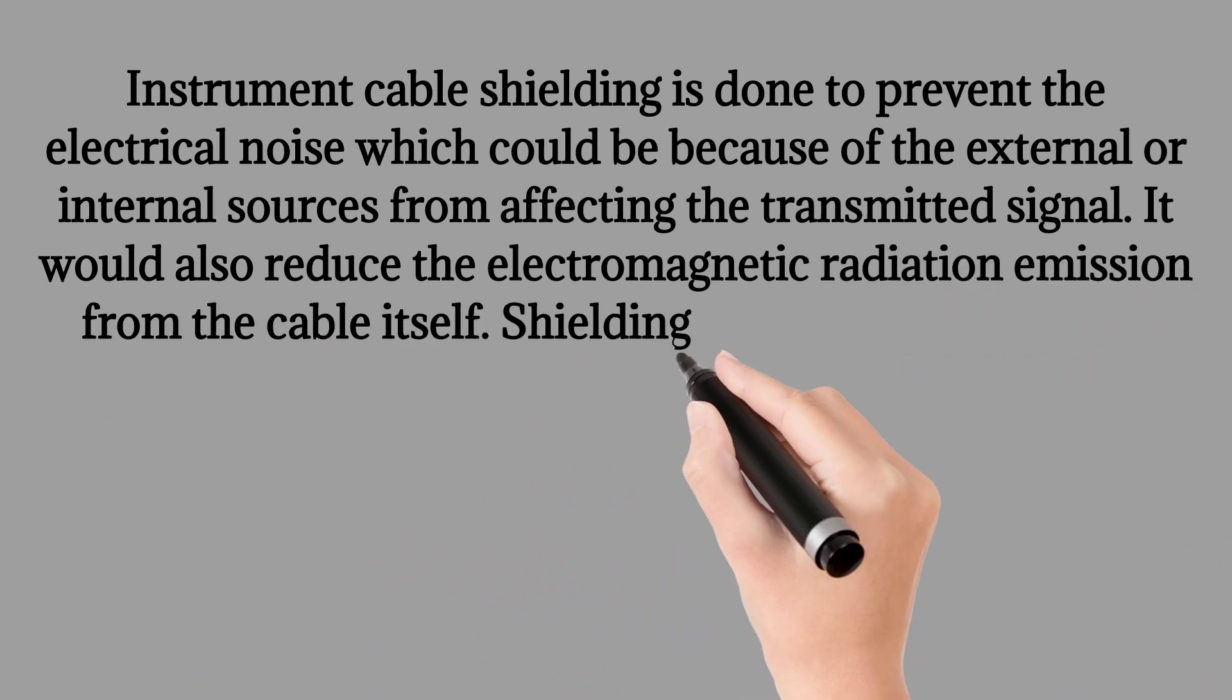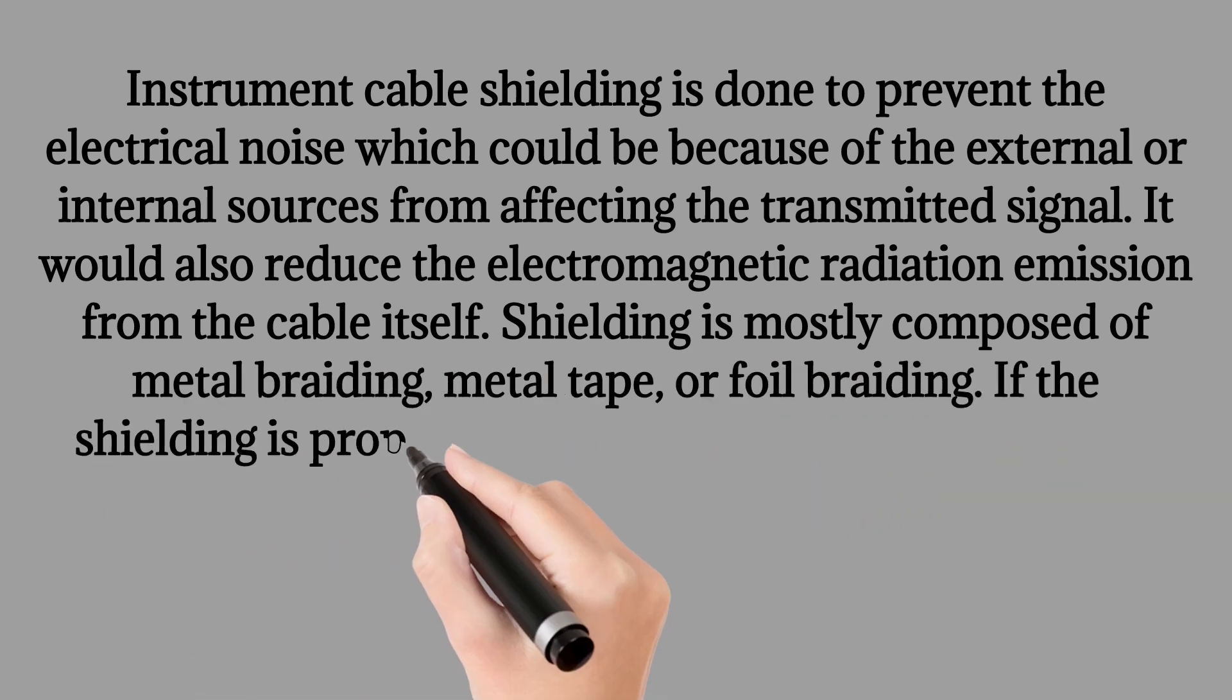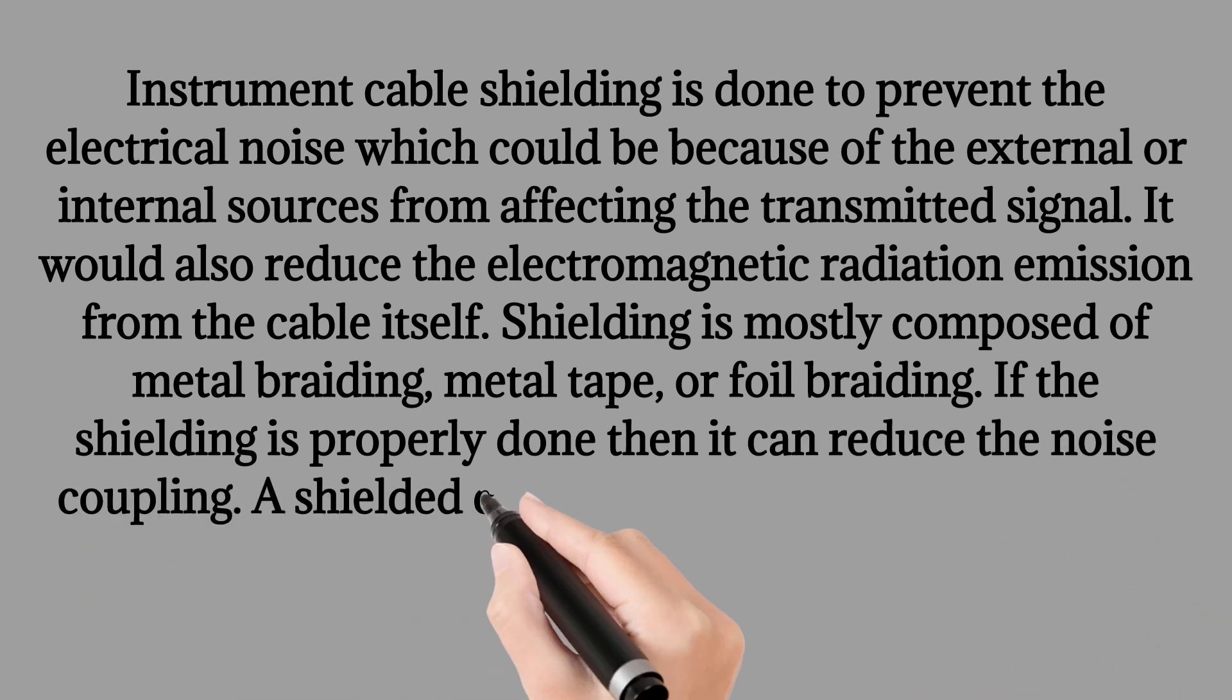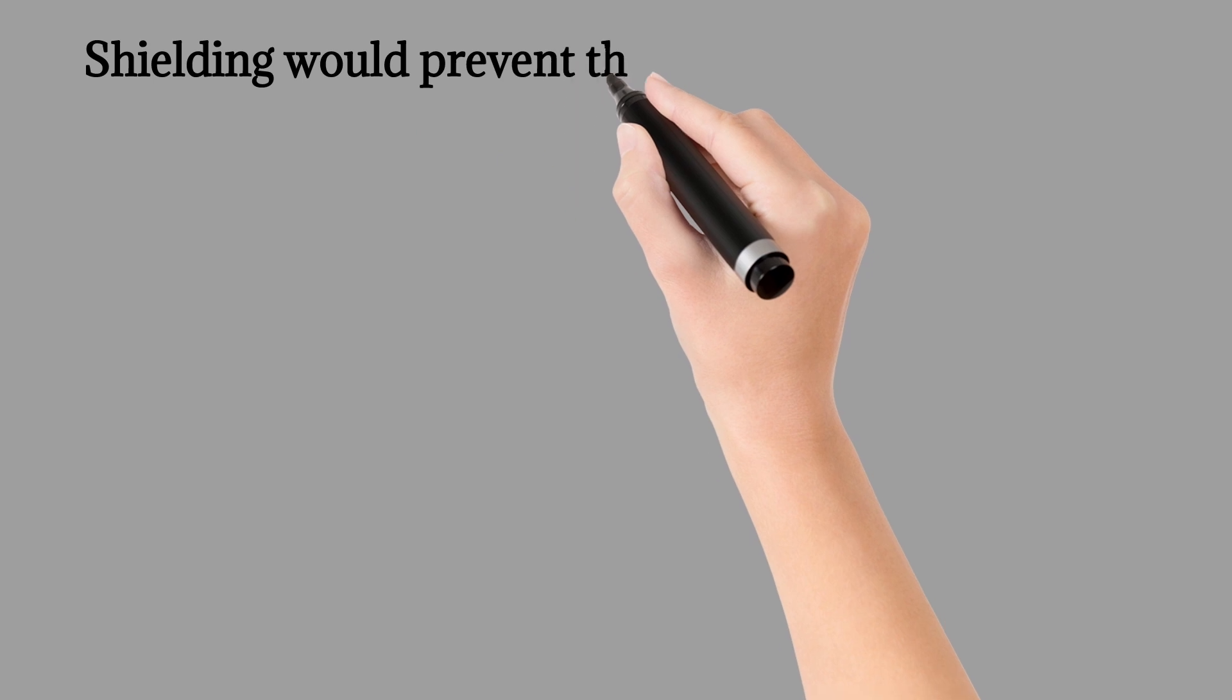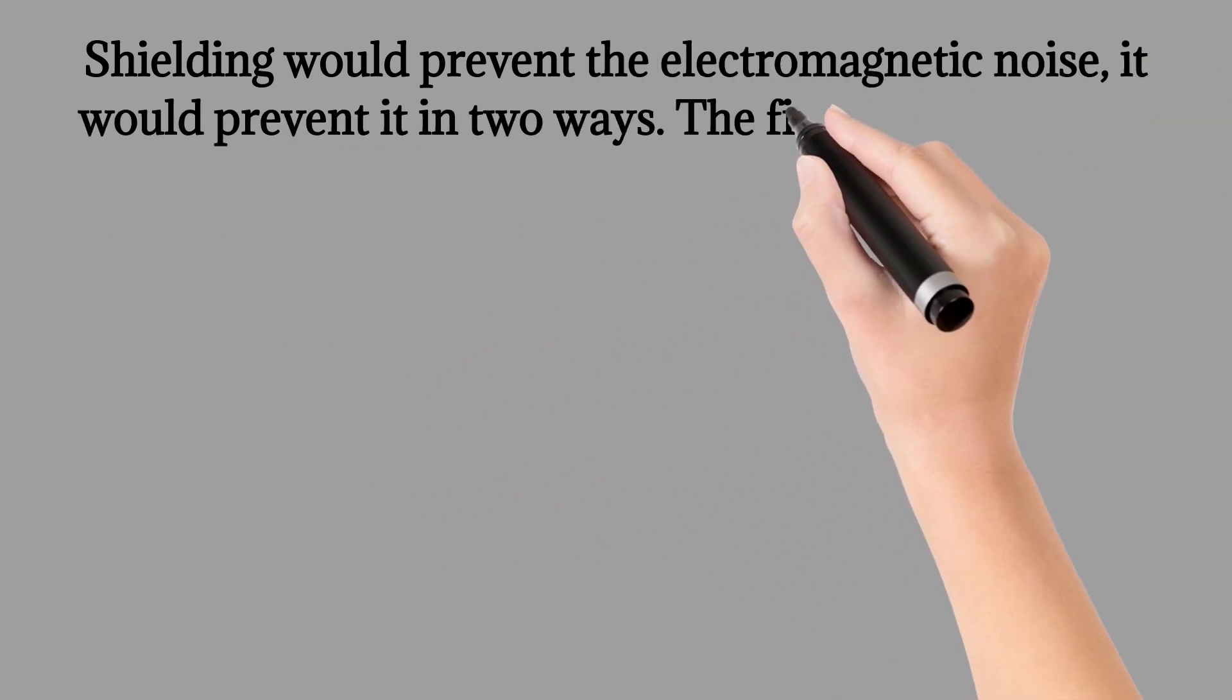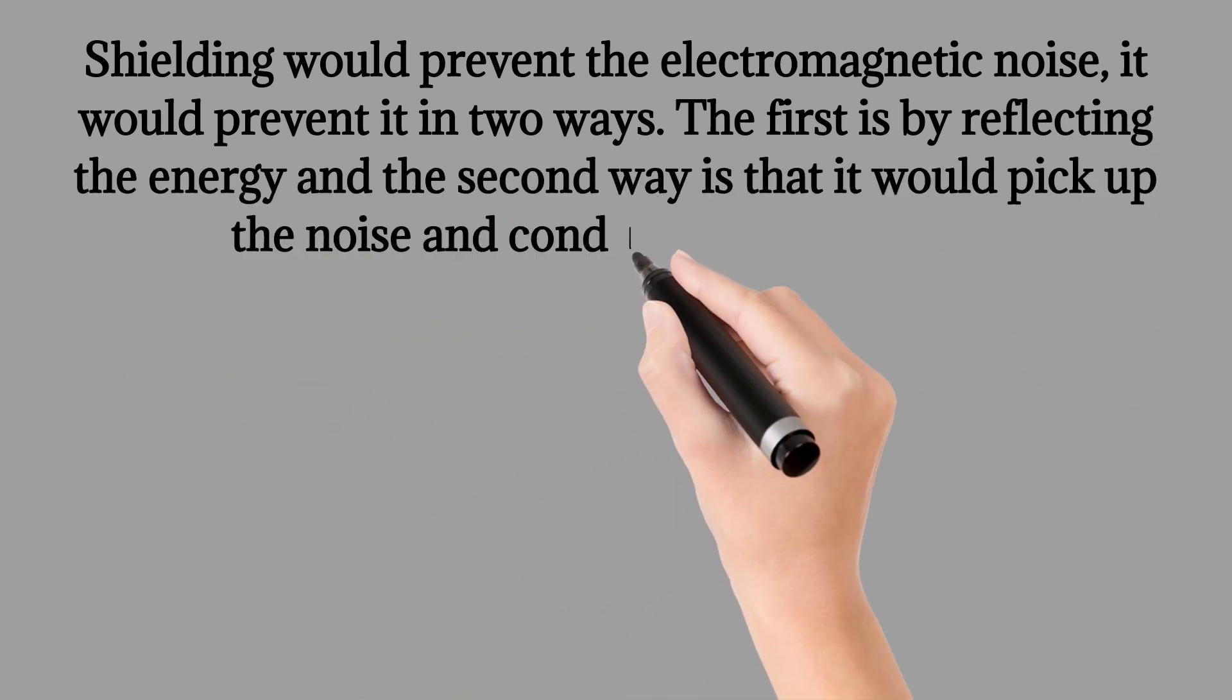Shielding is mostly composed of metal braiding, metal tape, or foil braiding. If the shielding is properly done then it can reduce the noise coupling. A shielded cable assembly could also feature a grounding wire called the drain wire. Shielding would prevent the electromagnetic noise. It would prevent it in two ways: the first is by reflecting the energy and the second way is that it would pick up the noise and conduct it to the ground.